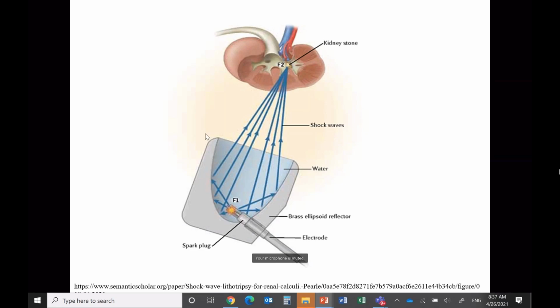Actually, this boundary isn't so strong, and the profile of this cavity is like an acoustical lens, and the sound waves are focused on the kidney stone, and in this way the stone is destroyed. So there is a problem of navigation: how to know where the stone is located. For this, we typically use sonography, for instance, or maybe an X-ray technique for navigation.